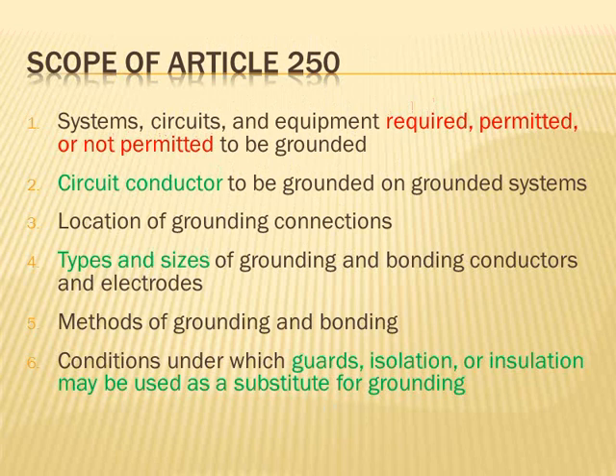Well, a delta is typically ungrounded, but if you are to ground a delta, phase B must be grounded. One phase, pick a phase, typically phase B. If it's a center tap delta, meaning they went to the guts of that delta, one transformer, pulled another wire, that center tap has to be grounded. If it's a Y, which conductor must be grounded in a Y? The center of a Y. So anyway, all these that we take for granted, guys, not directly from the sequence book.